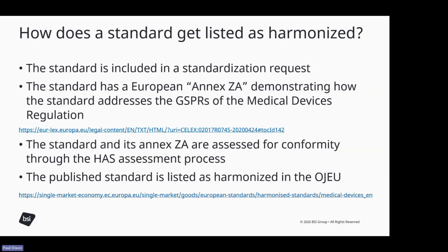So TC62 in IEC have a significant number. TC210 obviously have the risk management standards and many other standards for general aspects of medical device design. And then there are other technical committees with particular subsectors of medical equipment, such as ISO TC121 for respiratory equipment. The standard, as it's developed, has to have a European annex, colloquially known as an Annex ZA, that demonstrates how the standard addresses the general safety and performance requirements of the medical device regulation.